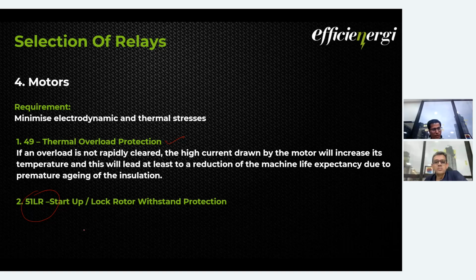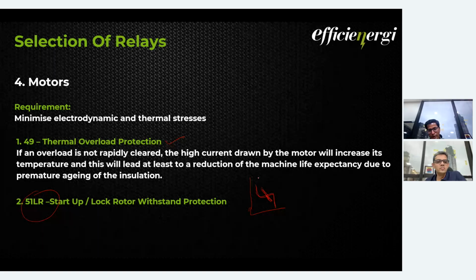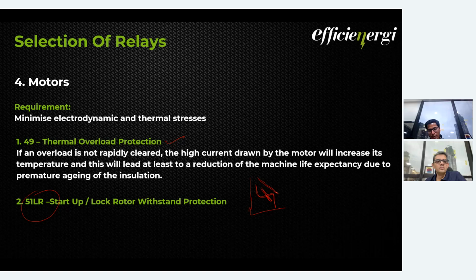Startup, you know, there is acceleration time required for the motor to accelerate, and at the same time there is a locked rotor withstand protection. In some cases, you will find in big motors that this startup time is actually greater than your locked rotor withstand time. So you cannot protect the locked rotor and at the same time have the starting curve protected. If I go for this kind of relay protection to avoid starting trips, my locked rotor withstand is below this, to the left. So I'm not protecting my motor for the locked rotor. Here we have different schemes that have to be worked on, that is LPS, which we will be talking about later.